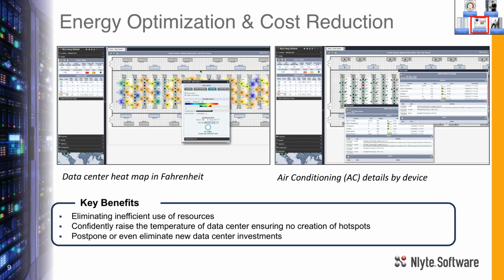The nice part about being able to see how much equipment is in each rack and what the load capacity is, is we can dial down our HVAC and electrical cost as well if we're able to turn down the cooling or raise the temperature. Ideally, hot aisle, cold aisle containment is ideal, but it's not feasible in all areas.